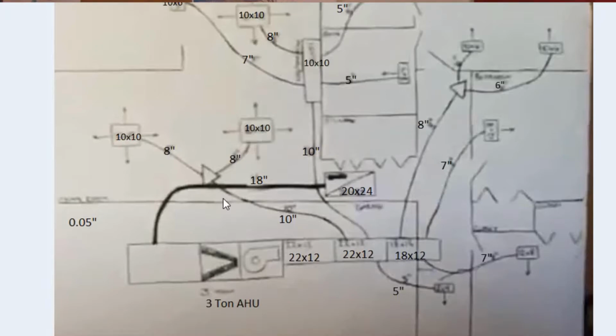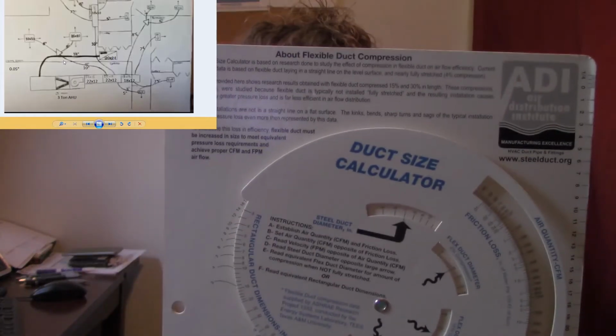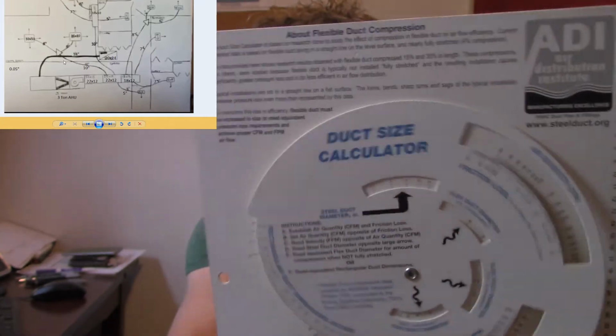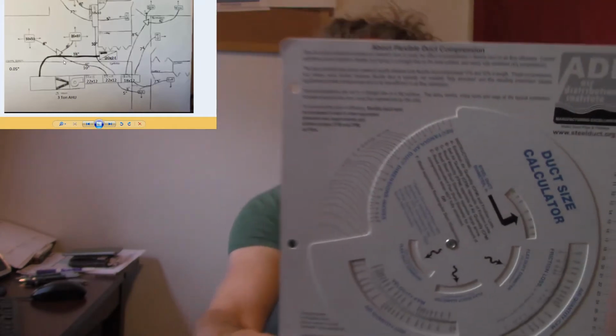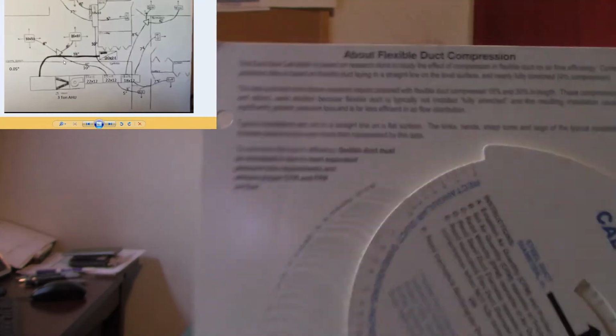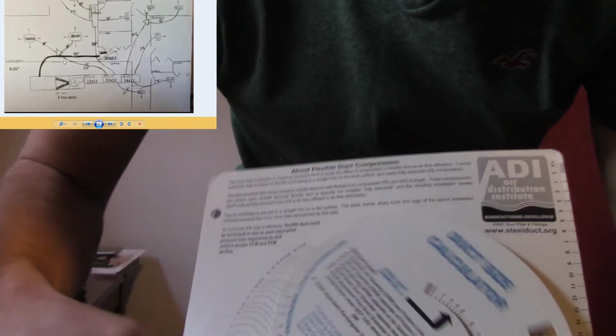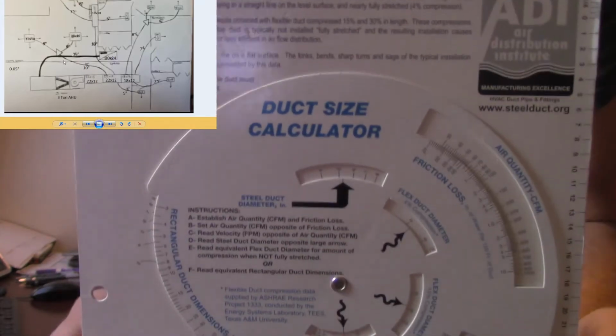The guy who is installing this was using a Trane ductulator. The Trane ductulators are very similar to all the other ones in that they can figure out dimensional duct based on friction rates and velocities. His ductulator looks very similar to this one. It's got a wheel that spins around the center, and you can base your ductwork off of what CFM you're trying to push. The nice thing about this one, as opposed to the one that he had, was that it actually is for flex duct. This one here is cheap and is plentiful.